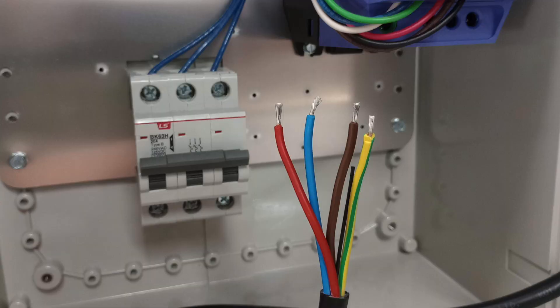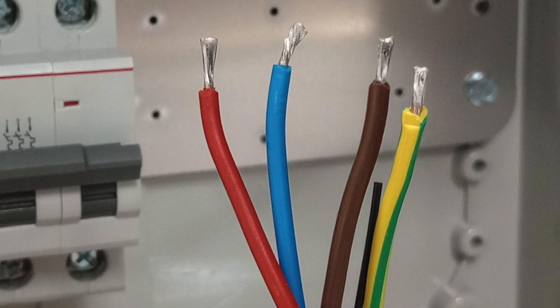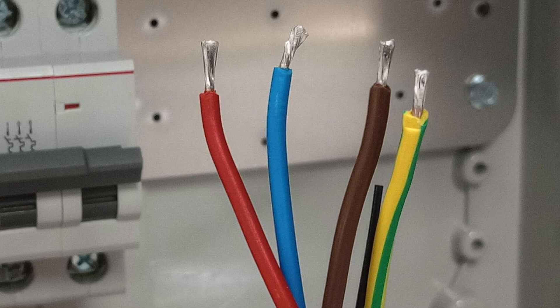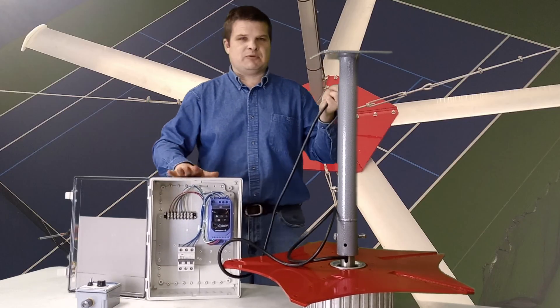You've got a cord coming out of it with four wires. The green and yellow one is your earth ground — your safety. The other three are blue, brown, and red. Those are your power wires and they go over to the variable speed drive that comes with the fan.